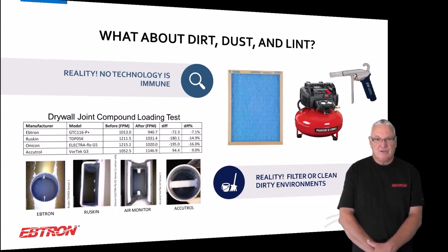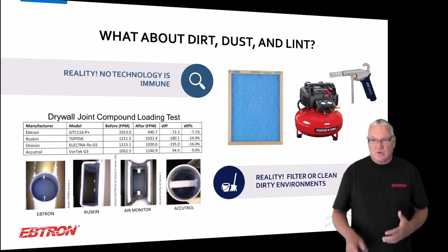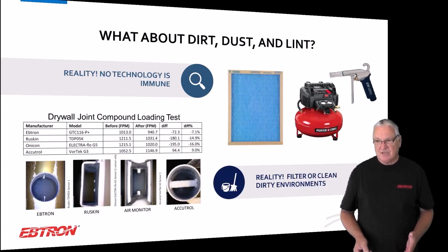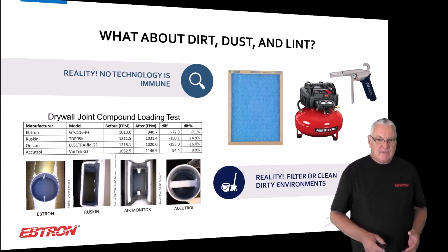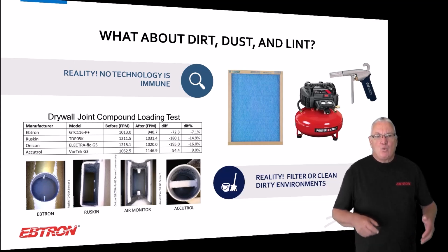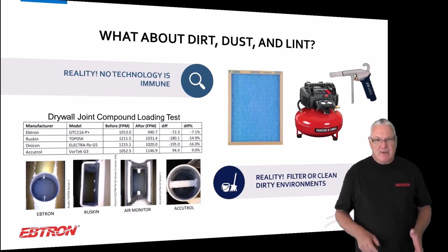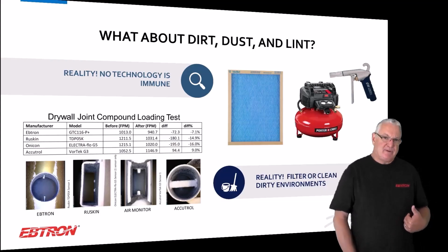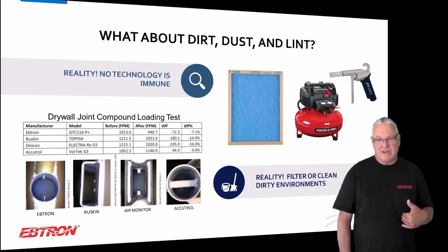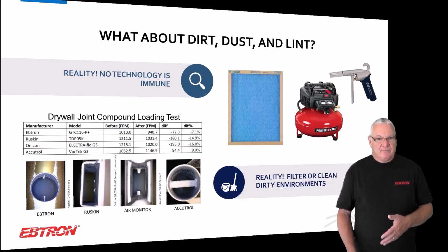If we want good control of ORs or ISO rooms or any of those types of spaces, and be able to independently control those as independent compartmentalized pressure zones, it doesn't matter who you're using or who you listen to, okay? We're going to need to provide a better environment. You can take one of our pieces of equipment, put it in the supply air, and I'm pretty confident that 20 years later, it'll be measuring what it was measuring the day you put it in, okay? It's a pretty good environment, okay?